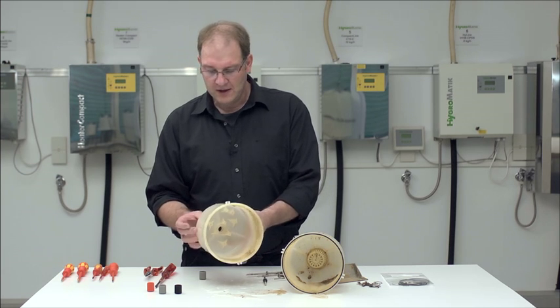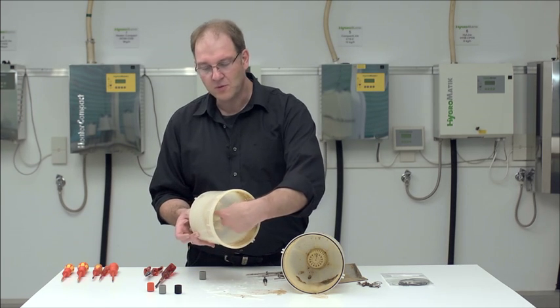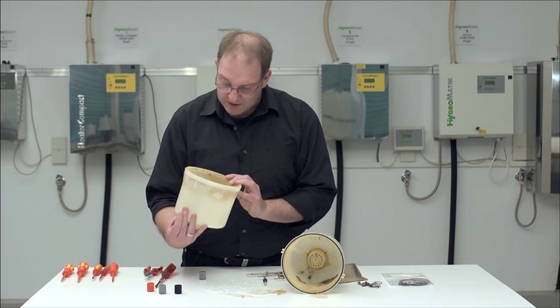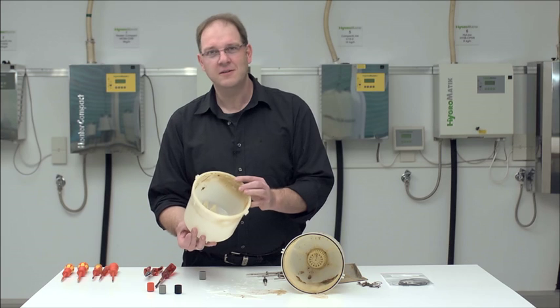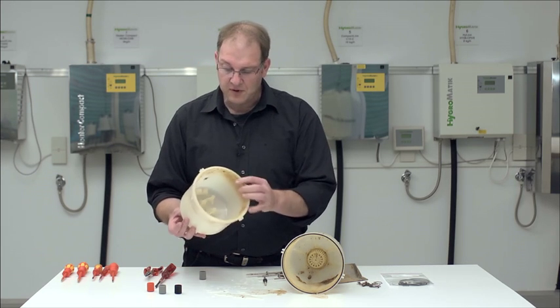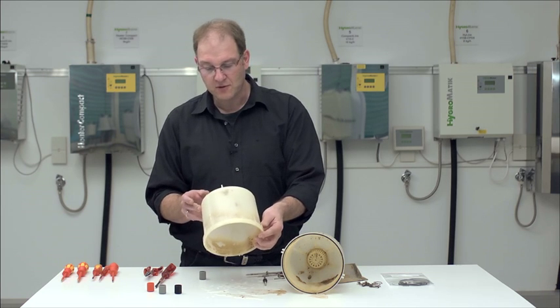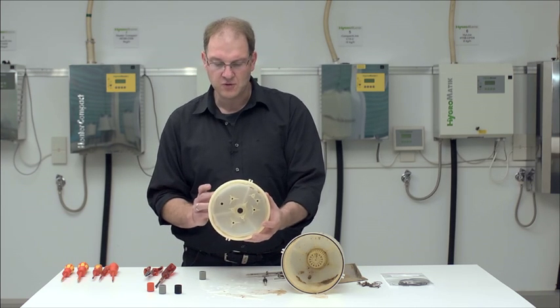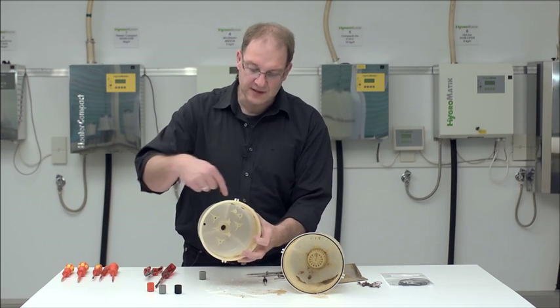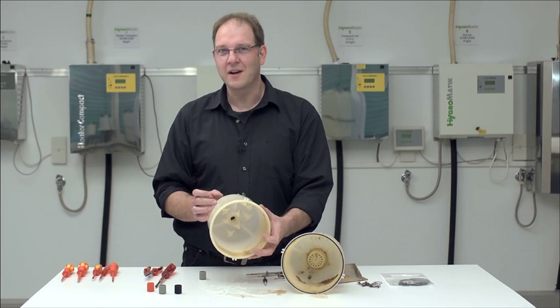I would really like to mention a certain point, and that is to please also perform the cleaning at the top of and inside the cylinder, because there too minerals as well as salts can deposit, and then sometimes up top here certain connections with the sensor electrode could be generated, which could at some point possibly produce interfering signals. Also here as well in the inside around the base of the electrodes, clean very well, that would be important.